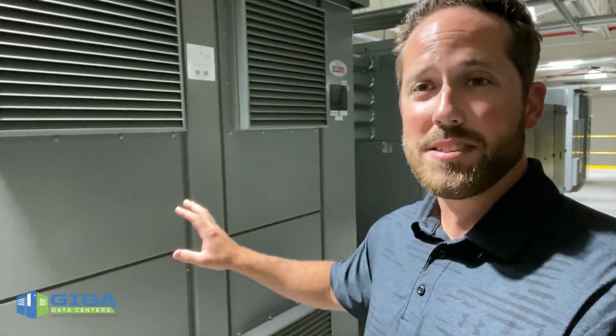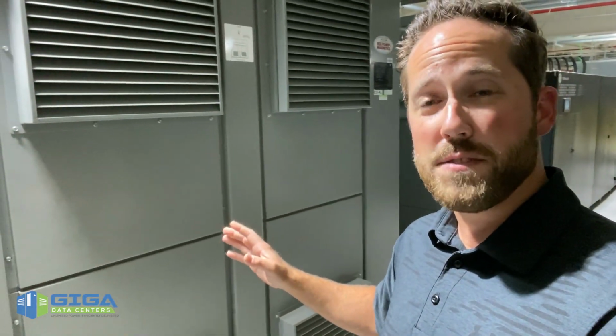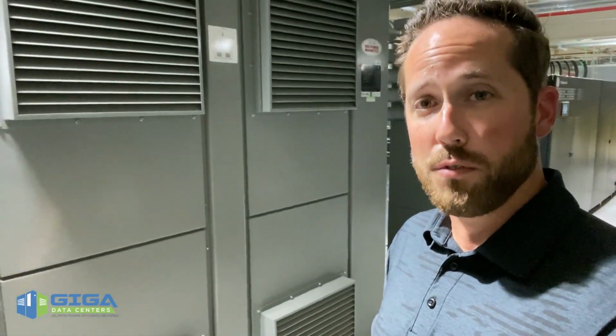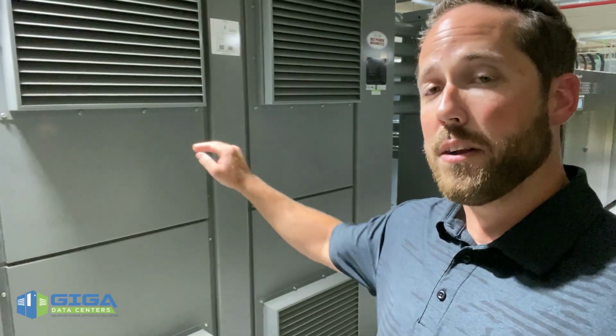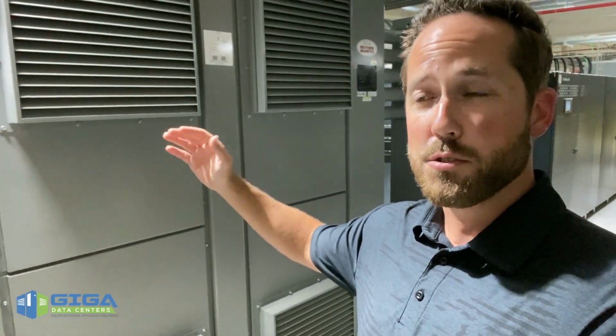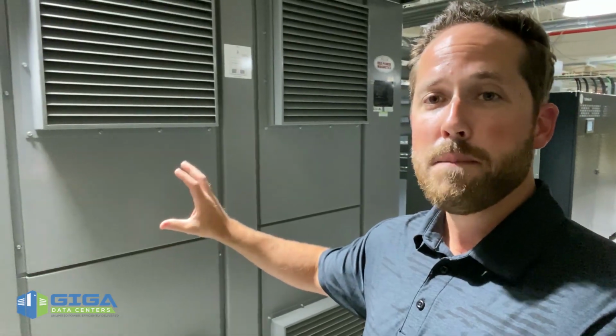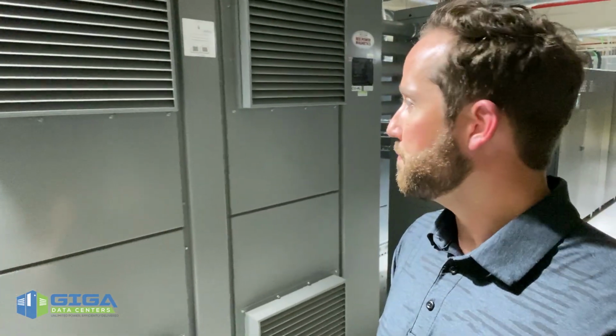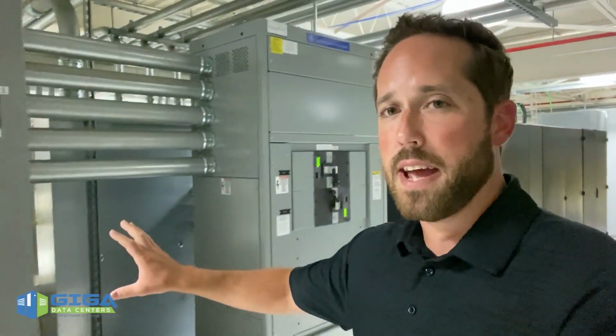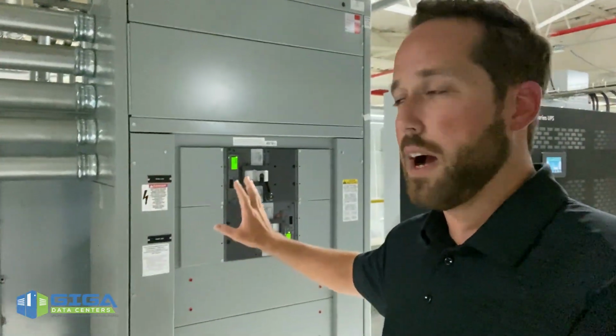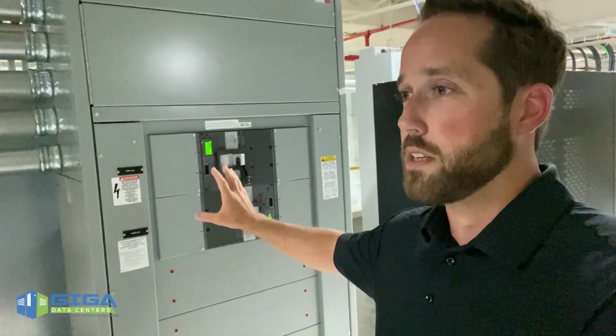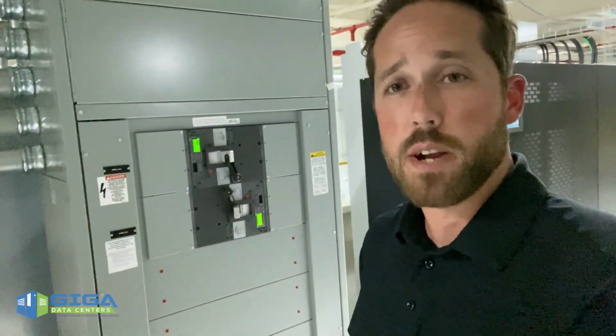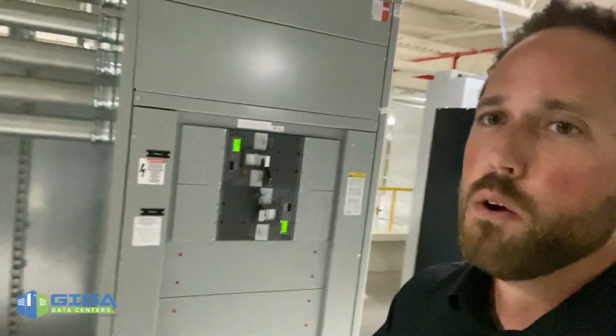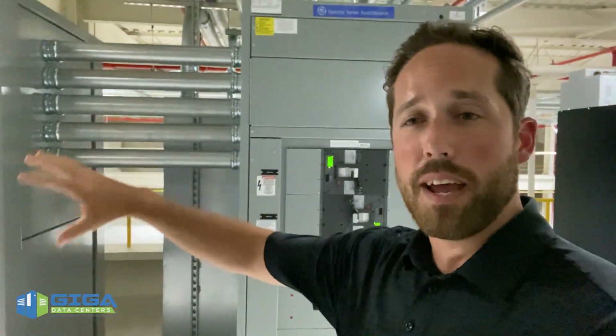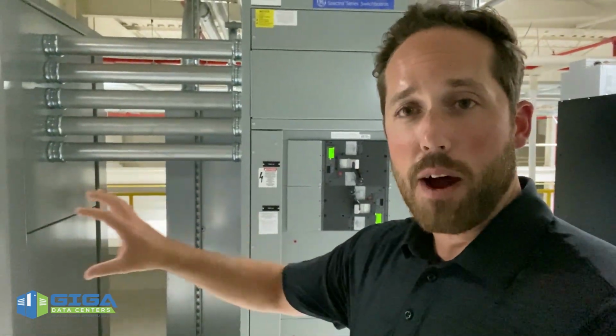The transformers are where we step down that power from 480 volts down to 415/240 volt power, and that's what's actually delivered out onto the floor to our customers. So 240 volt, 3-phase power is what we're delivering into those customer racks. After stepping that down, the transformers send that power over to our switchboards, which then deliver it out onto the data center floor. What we just walked through is a 1 megawatt run of our power setup.